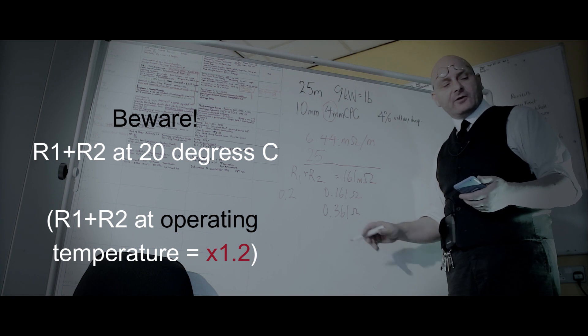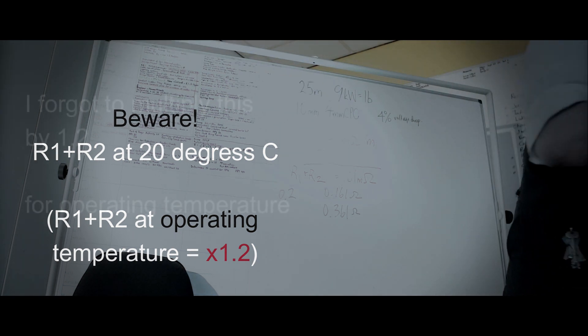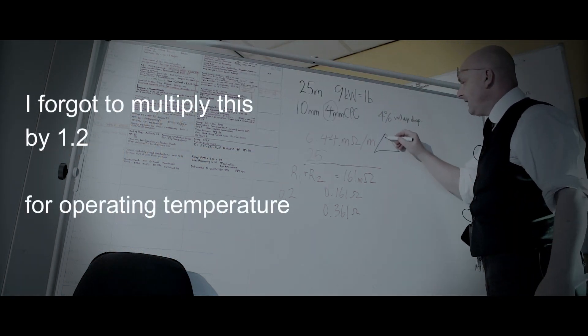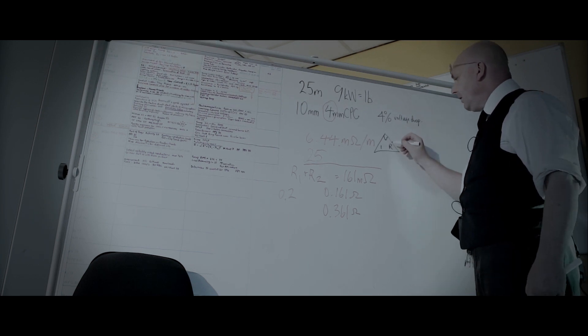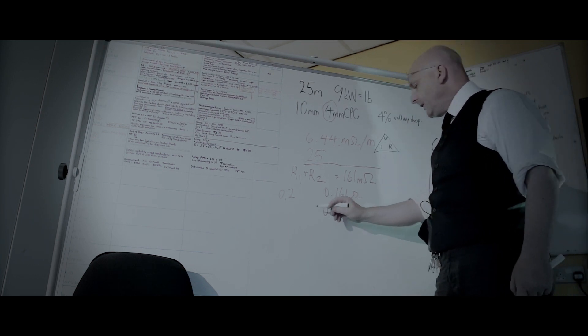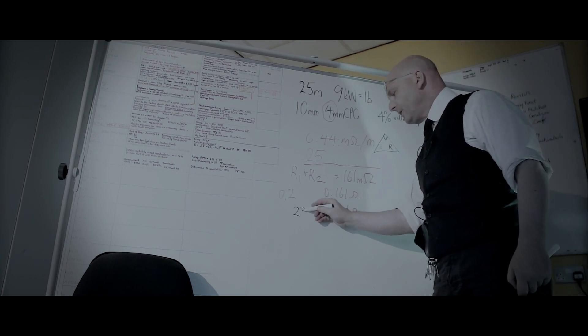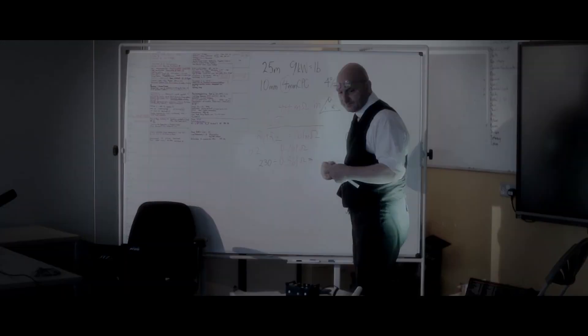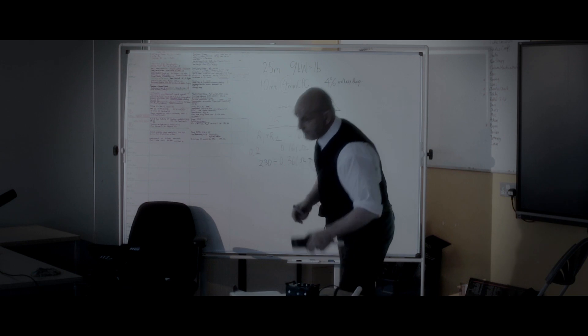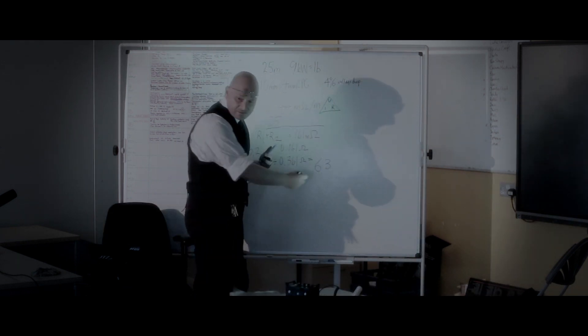How do we get a fault current from that? Using V equals IR, we divide 230 by 0.361, and we get 637 amps.